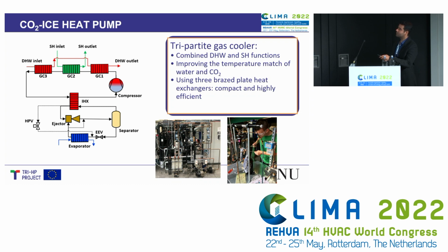On the other side, into the counterflow, we have the domestic hot water inlet temperature, the tap water at around 10 to 12 degrees Celsius, which is going to be preheated from 10 or 12 to, let's say, 40 degrees Celsius. It will also pass through gas cooler 1, reaching up to 65 to 70 degrees Celsius, to be supplied to the user.